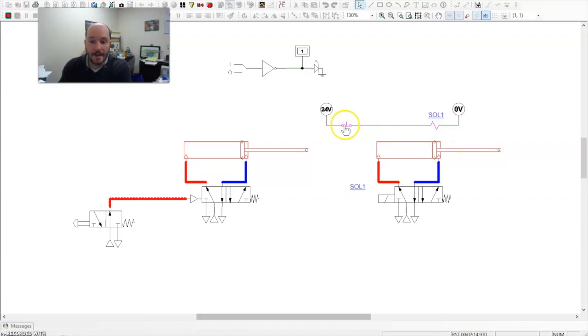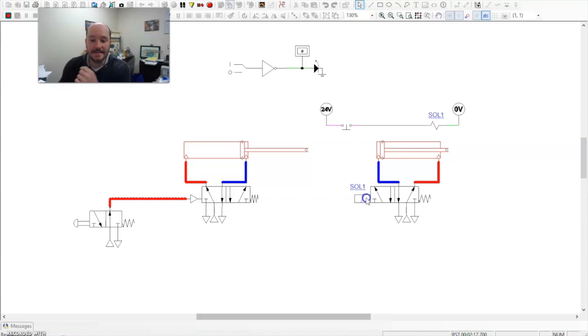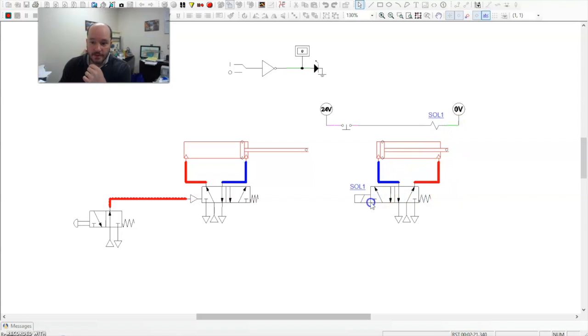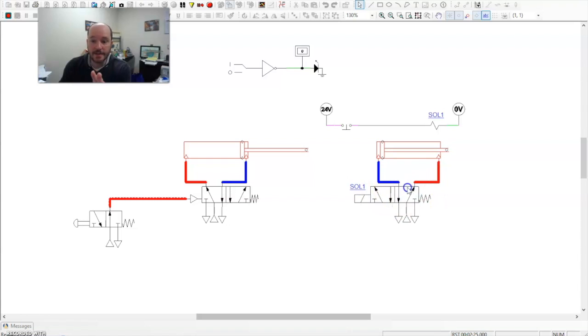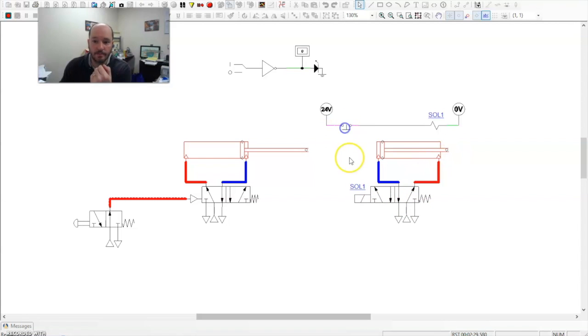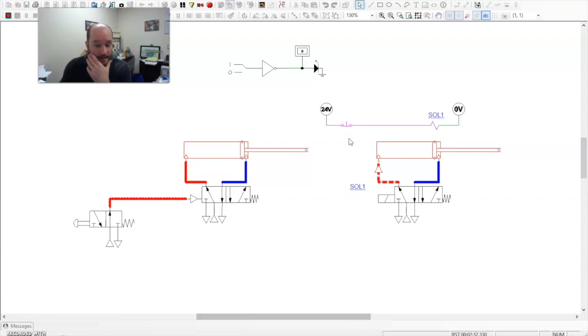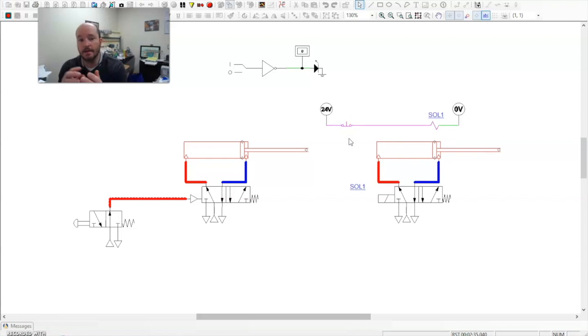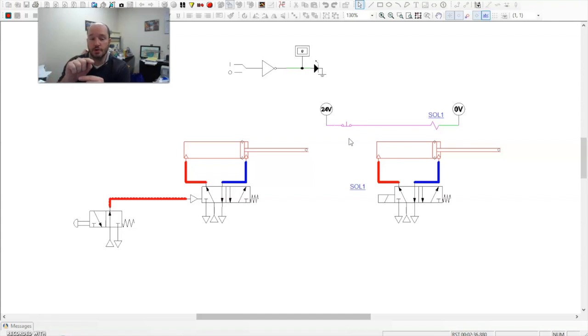When I push the button, that disengages solenoid one. This turns off. This turns off. The spring pushes this back. And the way the logic of the power circuit works, that retracts the cylinder. If I let it go, it goes back into its normal position, being normally closed. So it is true when I'm not activating it.